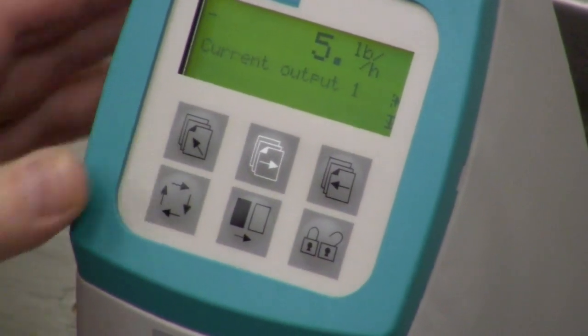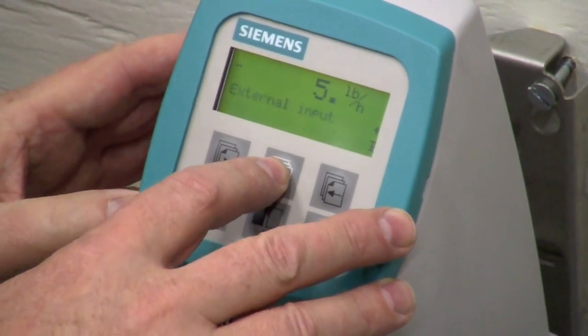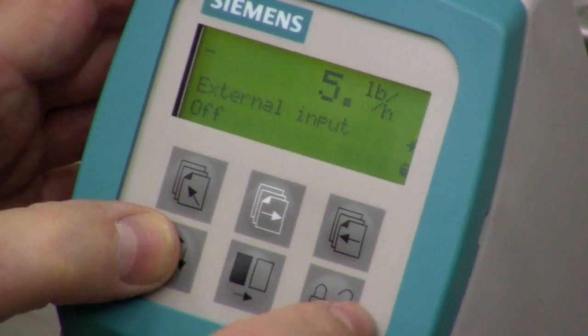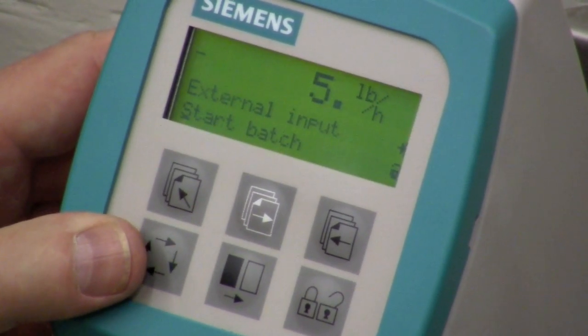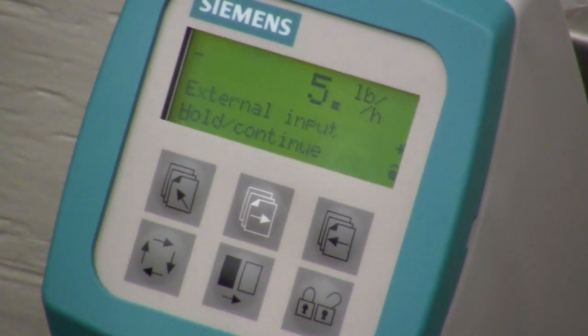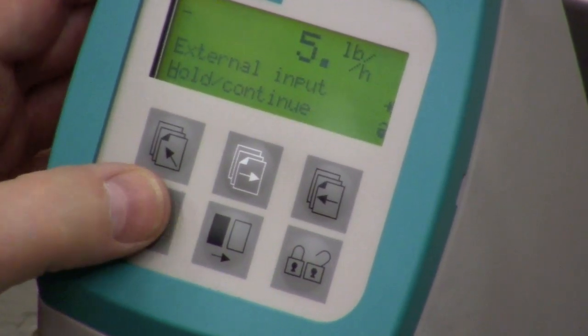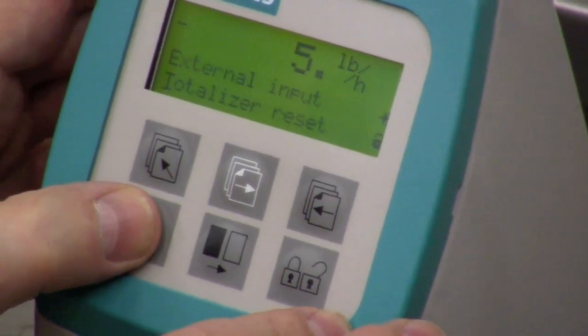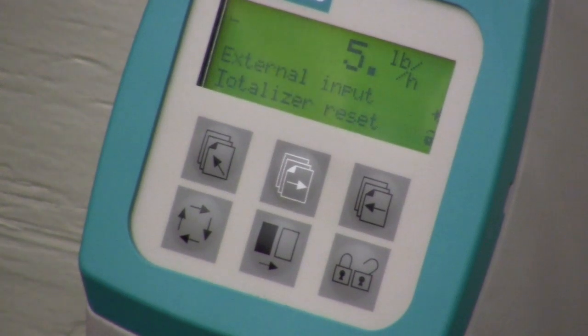There are others that allow dual current outputs, but this particular transmitter is only set up with a single current output. Next is external input. You can use this device as a batching device — externally you signal it to start measuring when you start your batch. You can also hold, continue, ramp up, stop, or slow down to control what your process is doing. You can also stop batch, zero adjust, and reset the totalizer from an external input or from the screen itself.